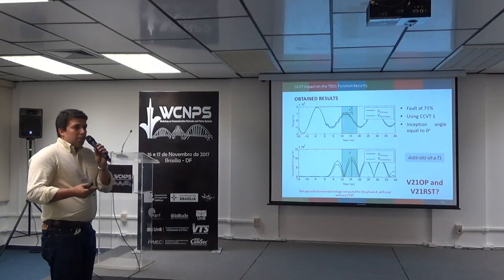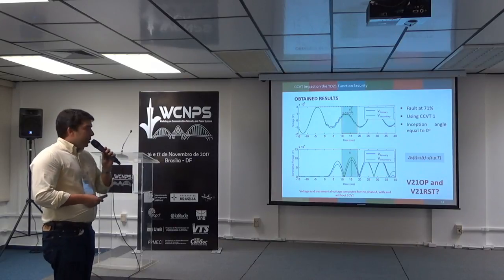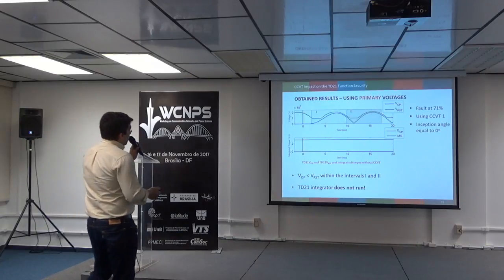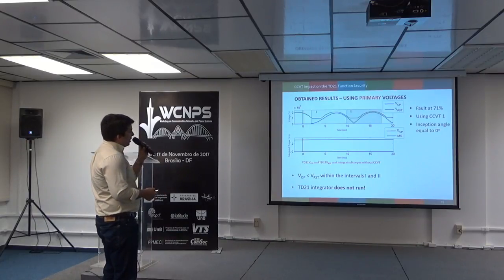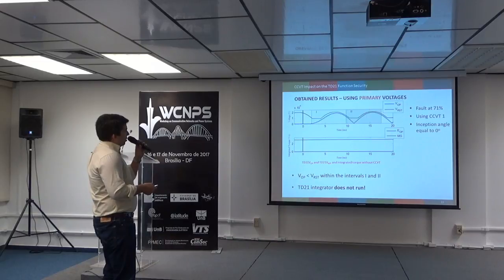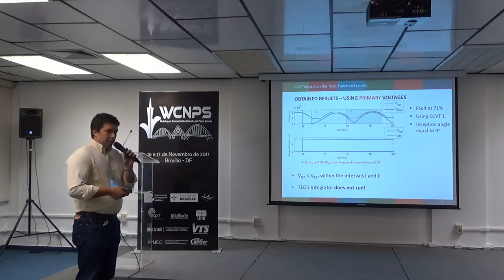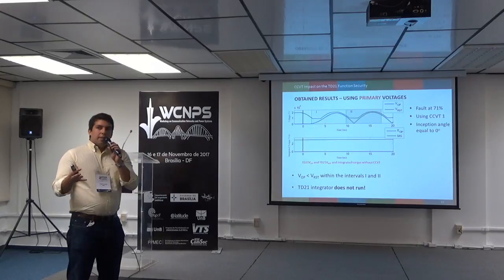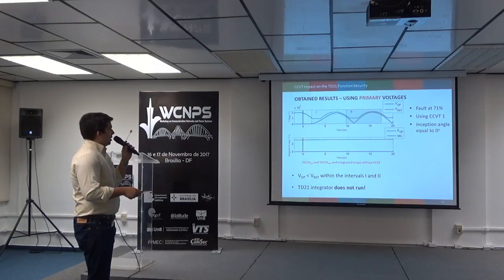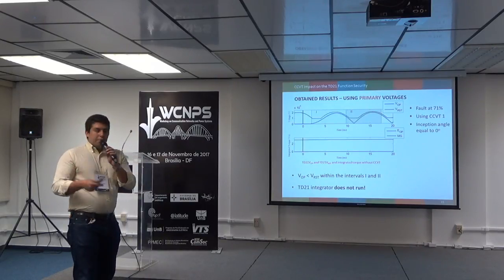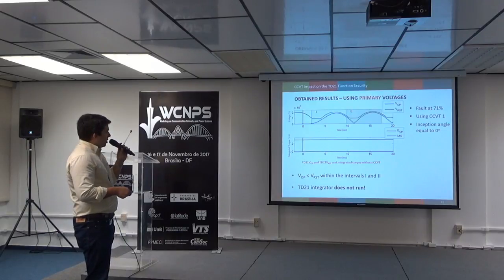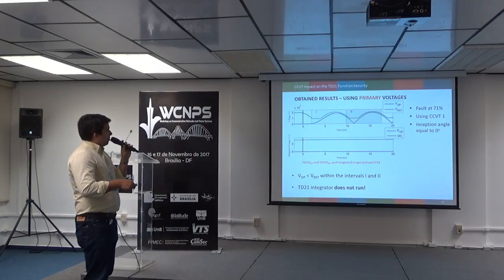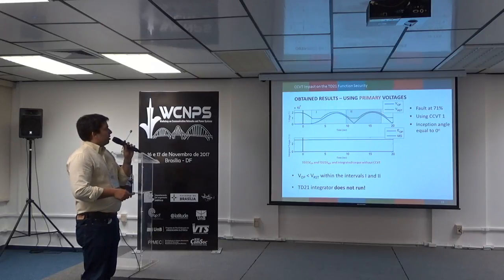And how will the operating signal and the restraining signal behave in this case? Let's see that. Using primary voltage for this same case, we have this comparison, so we will operate only when the operating signal is greater than the restraining one. In this case, the integrator would operate, but here it does not run, so we do not integrate. And the integrated torque does not exceed the security margin, so this function does not operate when we use primary voltage for a fault at 71%.